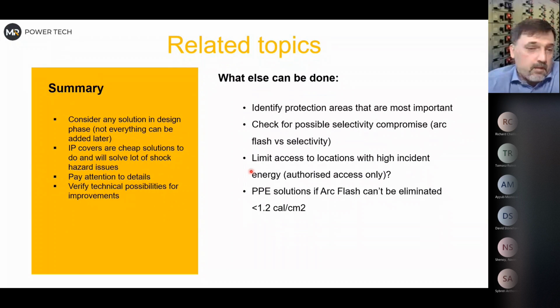We might limit access locations to only authorized personnel. So when we have high energy and we are afraid that someone will go there and hurt himself, generally, this is a general rule of thumb in Europe, but just to consider this, okay, it's a limited location, limited access. And of course, if we cannot reduce or eliminate energy below 1.2 calories, we will use PPE. And this is part of the solution.